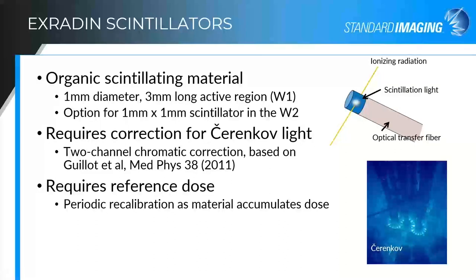Our scintillator is an organic scintillating material that produces light in the blue portion of the spectrum. Our original device, the W1, had a 1mm diameter and 3mm long scintillator coupled to a PMMA optical transfer fiber. With the W2, we provide both a 1x1 and a 1x3 fiber. You do have to correct for the Cherenkov light produced within the optical transfer fiber, so we've implemented a two-channel chromatic correction based on a publication from Guillot et al. in 2011, which I'll explain on the next slide.